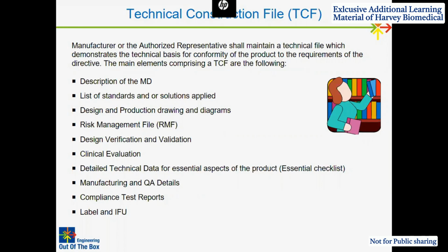Compliance test reports means various compliance test reports, like electromechanical and software. For software we have to comply with IEC 62304. And coming to the electrical, IEC 60601-1, 1-6, 1-9. So many standards are there. As we told, once you enter here, the list of standards, whatever standards we are maintaining here, all these standards should have compliance test reports.